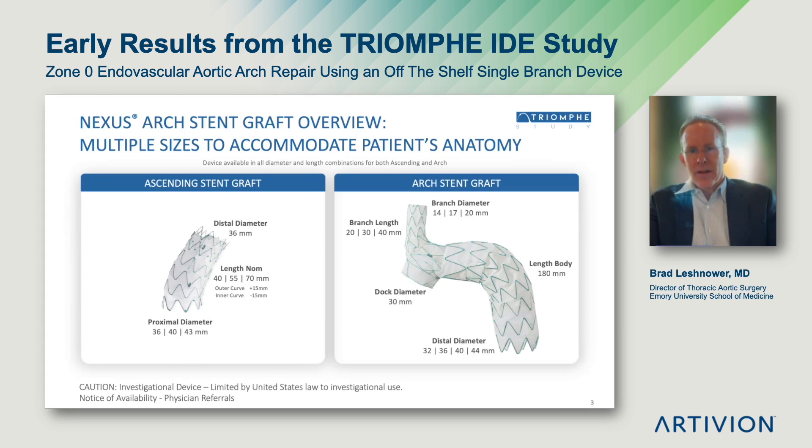The Nexus arch stent graft system is a modular, off-the-shelf system designed to treat aortic pathology in the aortic arch. It comes in two components. There's a main body arch stent graft that has a single branch integrated into the design that comes in varying lengths of 20 to 40 millimeters and varying branch diameters of 14 to 20 millimeters. The next component is a dock that is 30 millimeters in diameter, designed to be placed in the distal ascending aorta. The main body of the graft is 180 millimeters and comes in varying distal diameters ranging from 32 to 44 millimeters.